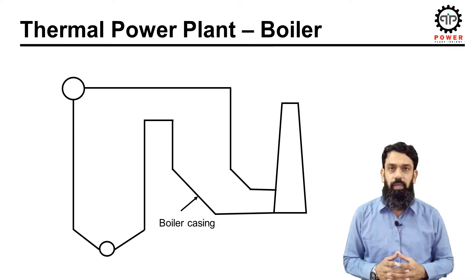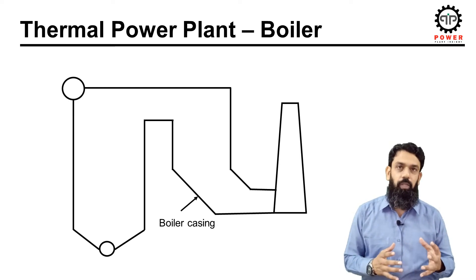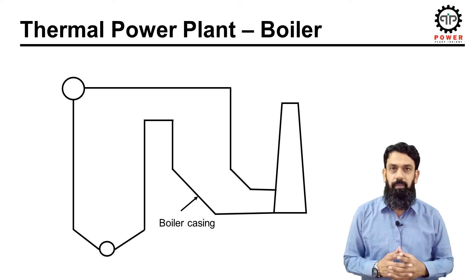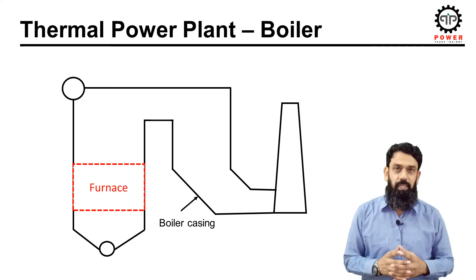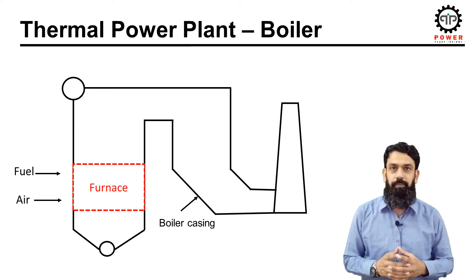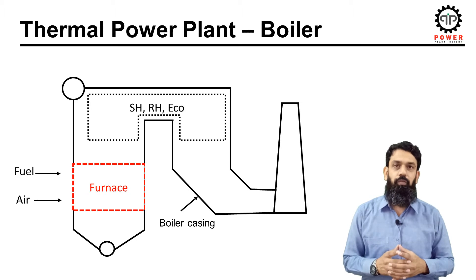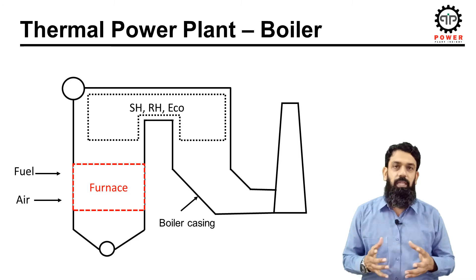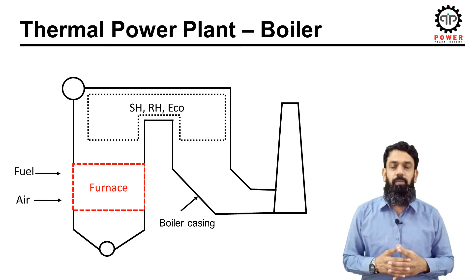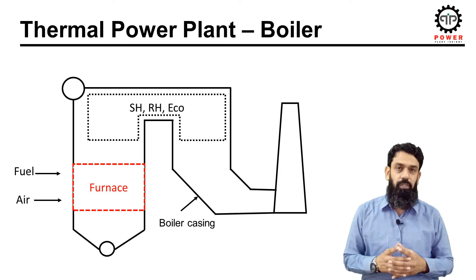This is the casing of the boiler that forms the outer covering for the boiler internals. This part is called the furnace — combustion takes place in this section using fuel and air as input. Tube bundles for the superheaters, reheaters, and economizers are located in this part of the boiler. As a result of combustion in the furnace section, heat is absorbed by the working fluid in the tubes of the furnace, which are called water walls, and the process of steam generation starts.